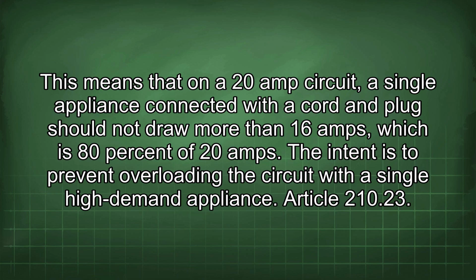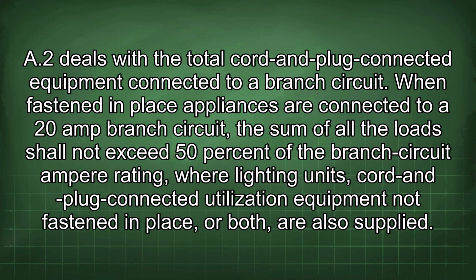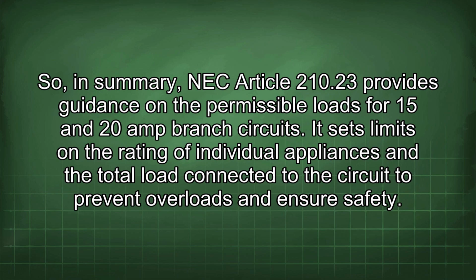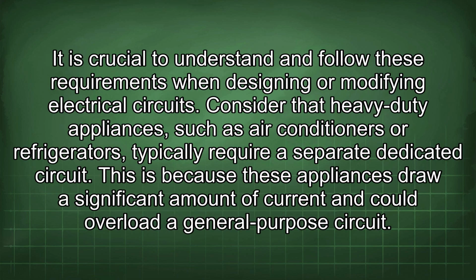Article 210.23 A2 deals with the total cord and plug connected equipment connected to a branch circuit. When fastened in place appliances are connected to a 20 amp branch circuit, the sum of all the loads shall not exceed 50% of the branch circuit ampere rating, where lighting units, cord and plug connected utilization equipment not fastened in place, or both, are also supplied. So, in summary, NEC Article 210.23 provides guidance on the permissible loads for 15 and 20 amp branch circuits. It sets limits on the rating of individual appliances and the total load connected to a circuit to prevent overloads and ensure safety. It is crucial to understand and follow these requirements when designing or modifying electrical circuits.